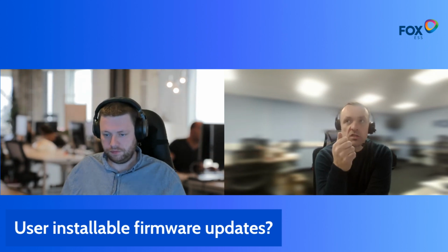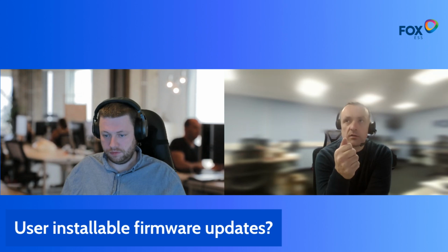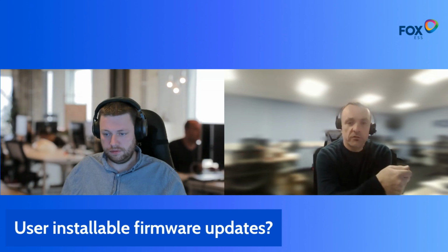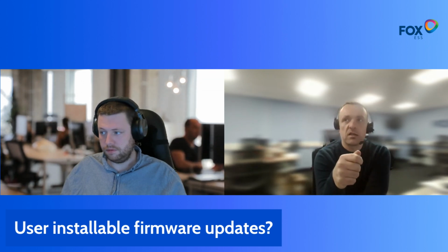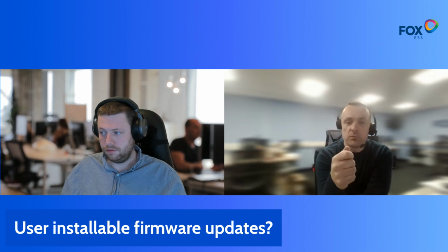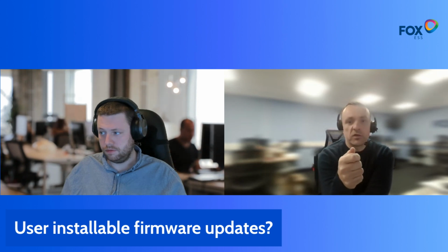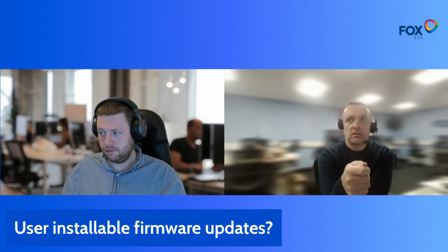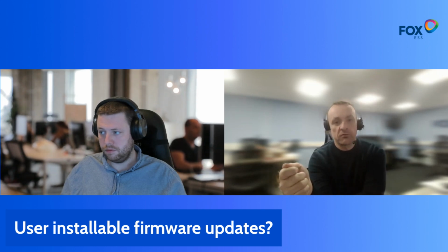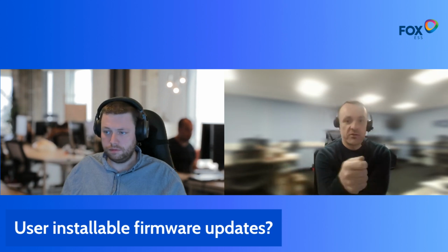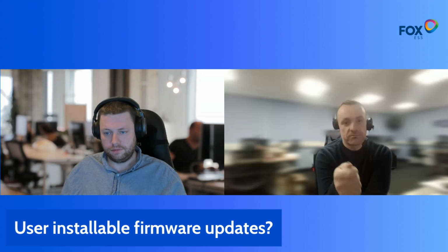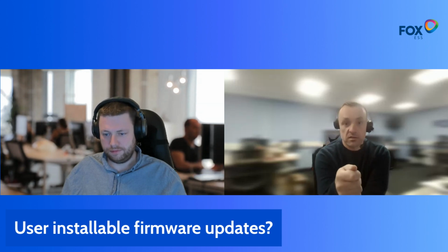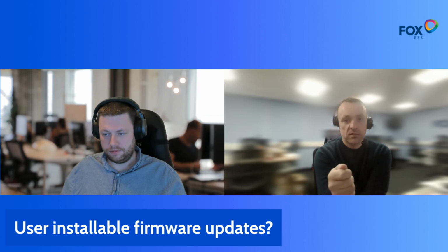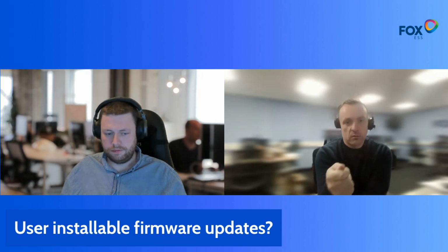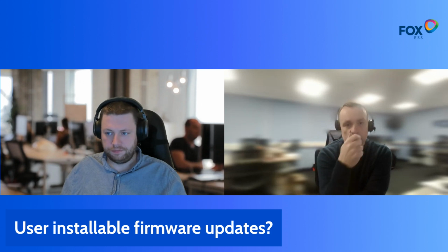There's also a small chance that during a firmware update the comms are lost and there's a failure. Normally that wouldn't be a problem, because it just reverts to its previous state if comms are lost during the data transfer. But in a small number of cases it can be a problem. So even if it's just 0.1% of the 3 million plus unnecessary firmware updates rolled out, using up server resource and other things, that can cause the inverter to fall over during the process. So when assessing the risk of opening up firmware updates to everybody, you can see where I'm going with this.